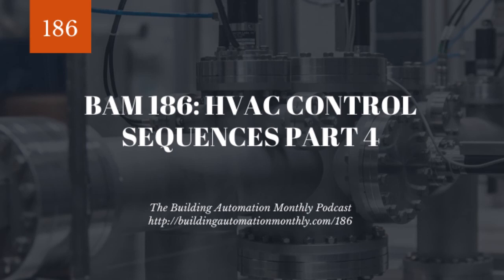Cooling valve, pretty straightforward, right? We're going to drive that to a discharge air set point. Now, typically what we will do is drive a discharge air set point to maybe 55, 53, 52 degrees, depending on our humidity projections and at which point we're going to reach saturation and have the effect of draining the humidity out of the airstream to the point where we're at our relative humidity goal that we want when we reheat the air. Because the air is typically going to be reheated by the boxes within the space.